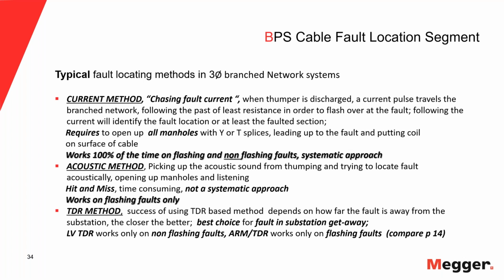And then you go to the next Y splice and do the same thing. So you leapfrog from manhole to manhole, but only those where you have Y splices. And some people don't like it too much because they think it's too time consuming. But I would say this, from what I have seen, on average, you save time doing it.